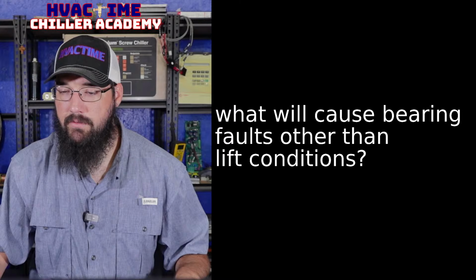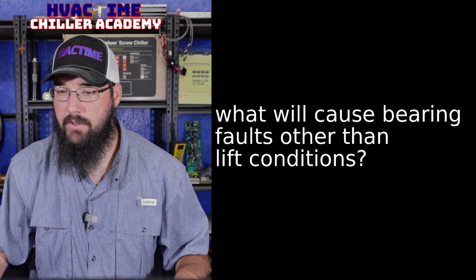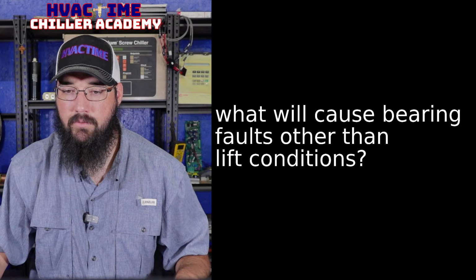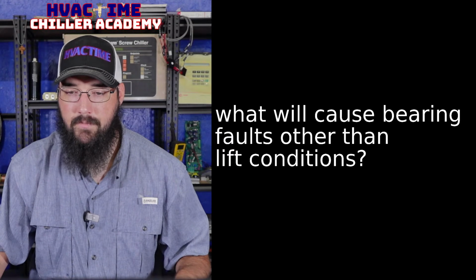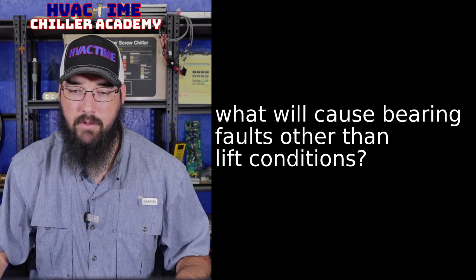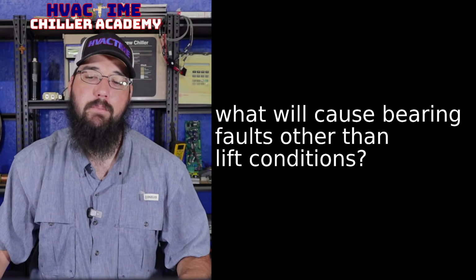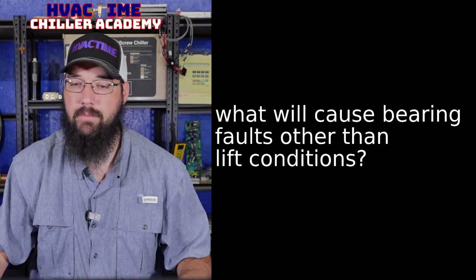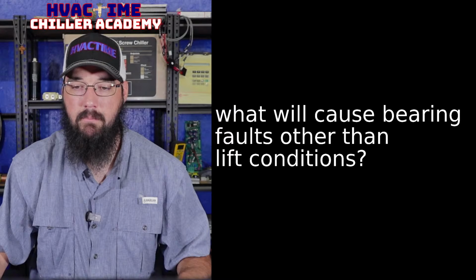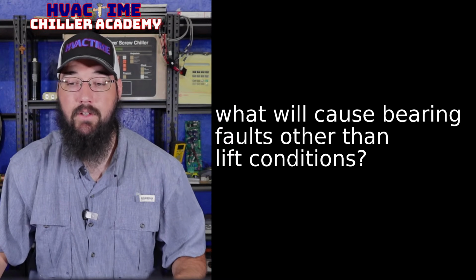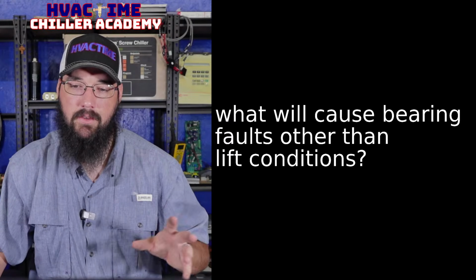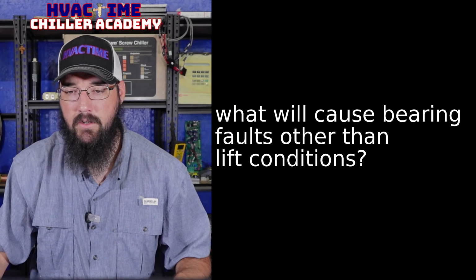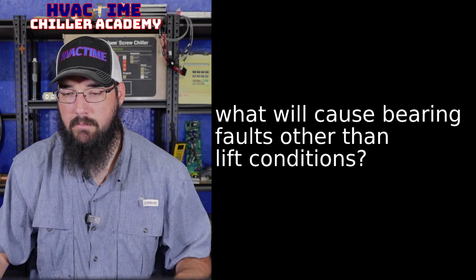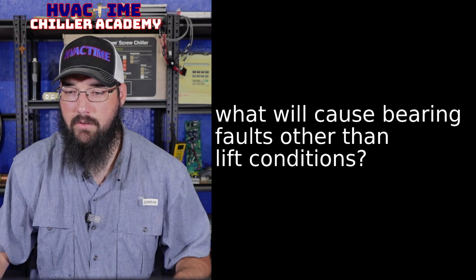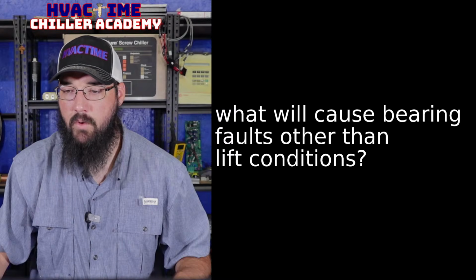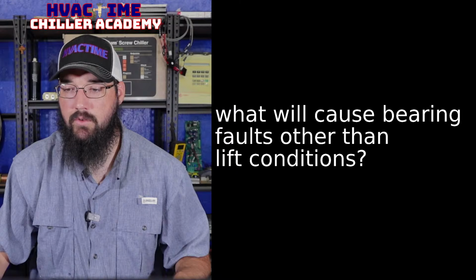Bearing calibration, see if it's off. You don't need to save it to the EEPROM; validate, compare it. Yeah, you've got to be really, really careful with those bearing calibrations. I've had people go in and do a bearing cal on maintenances and completely screw it up, and take a perfectly good compressor and have it just not function without getting the calibration correct. Bearing calibration shows up bad. Smaller than normal, sometimes out of place. Only the front bearing. Everything else tests good electrically.